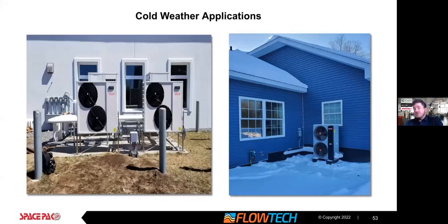Cold weather application. Very common question we get, hey, when do they shut off? They don't. They never will shut off. As we understand, they just ultimately reduce, and at some point at ultra low temperatures will equal a COP of 1. But they always will contribute at least that. So a couple of case studies: the one on the left is a research station where our old low ambient unit replaced some existing equipment that had failed, and that kept that classroom warm all winter. I think this was in Antarctica or some really extreme climate.